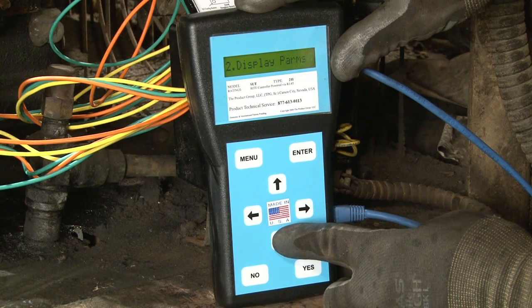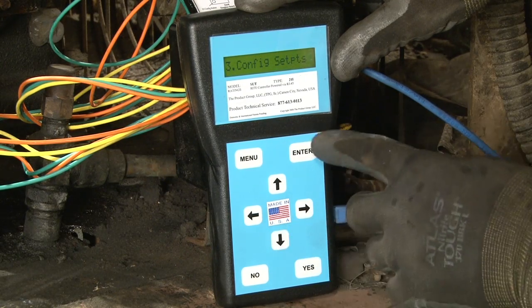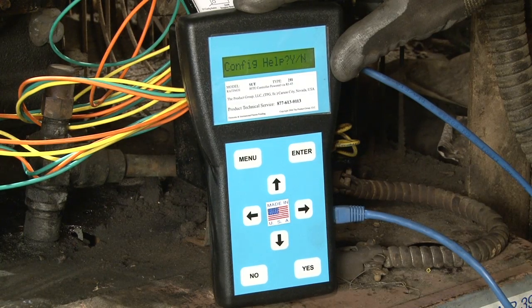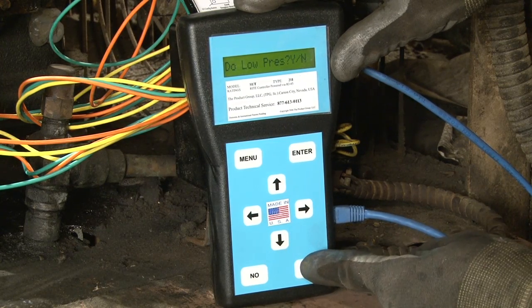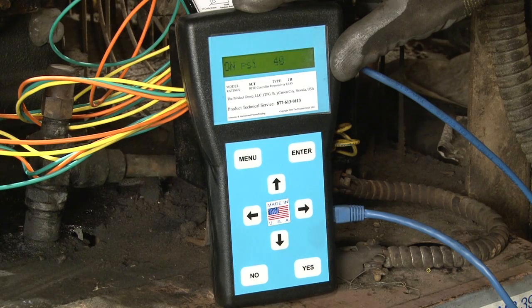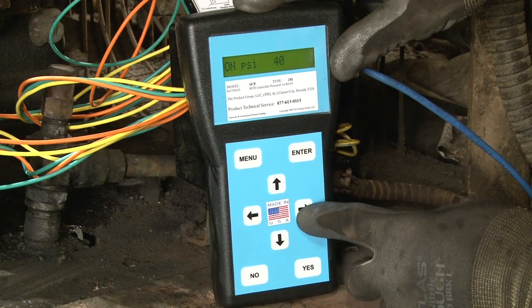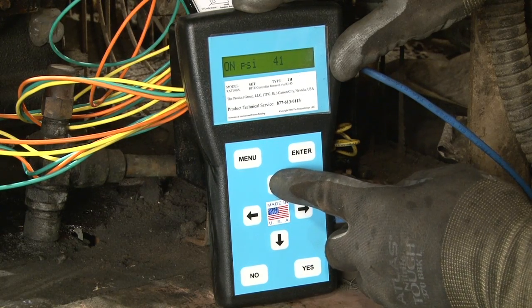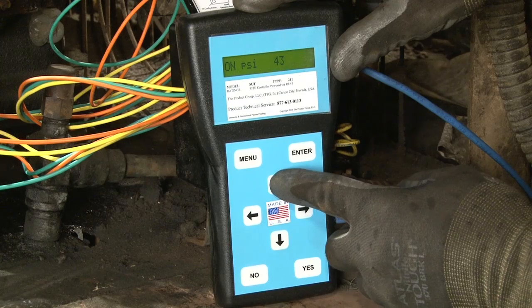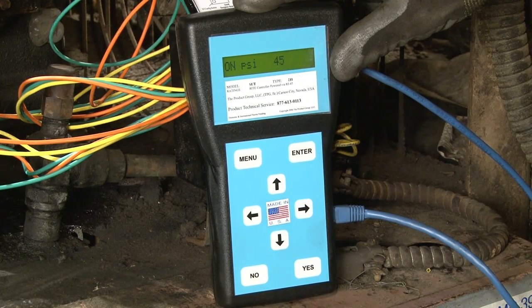We now move to menu item number 3, configure set points. We press the enter button. We won't use any configuration help, and we're going to put our own set points in, so we won't use the defaults. We won't be using head pressure control, but we will be doing low pressure control, so we answer yes. It asks us for the on pressure set point. We're going to change it from the default setting of 40 psi to 45. When we're there, we press the enter button.